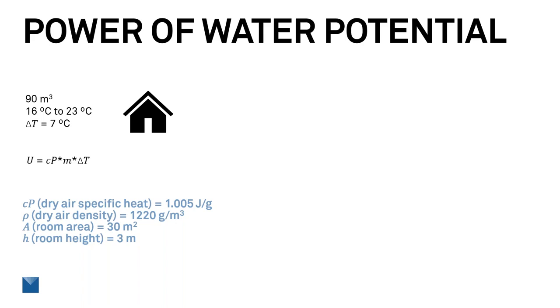That's a temperature rise of 7 degrees Celsius. And again, we don't have temperature to guide our heating, so we just have to start adding heat to get ourselves to a more comfortable temperature. Let's say in this example, this is a dry room, no relative humidity. If you look in this lower right-hand corner, we have all these variables we have to take into account to figure out how much heat to add to bring it to that comfortable temperature. One important variable is the specific heat of the air, but then there's also the volume of the room and the density of the air.